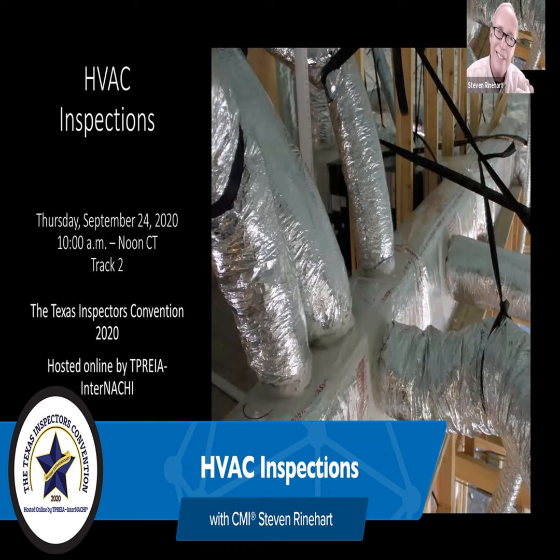I had a gas water heater like this one in my laundry room. I'd run a load of clothes, turn the dryer on, sucking 300 CFM of air out of that laundry room. It'd make noise. I'd close the door. The laundry room makeup air was my water heater flue. Couldn't figure out the first year why my water heater was covered in soot. It is now a Rinnai tankless, which got rid of that problem. But these are old and have a problem. They can still work, but they're typically in the house, and there are pressure problems that make those have an issue.